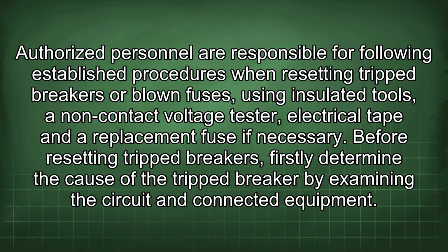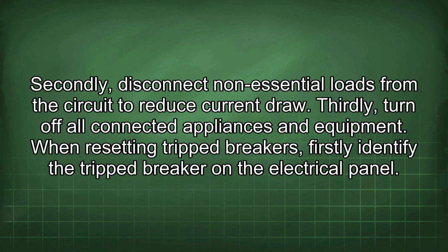Authorized personnel are responsible for following established procedures when resetting trip breakers or blown fuses using insulated tools, a non-contact voltage tester, electrical tape, and a replacement fuse if necessary. Before resetting trip breakers, firstly determine the cause of the trip breaker by examining the circuit and connected equipment. Secondly, disconnect non-essential loads from the circuit to reduce current draw. Thirdly, turn off all connected appliances and equipment.